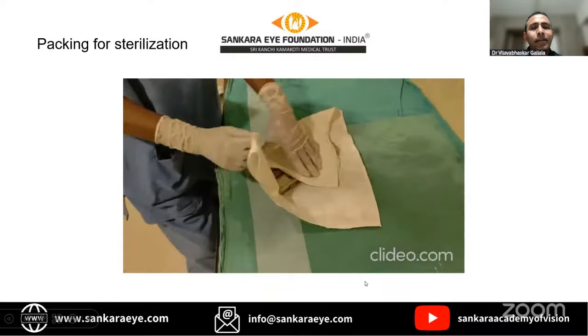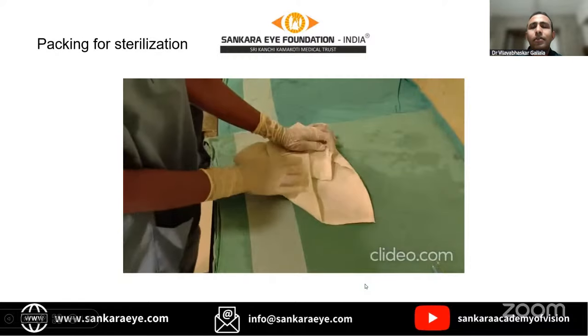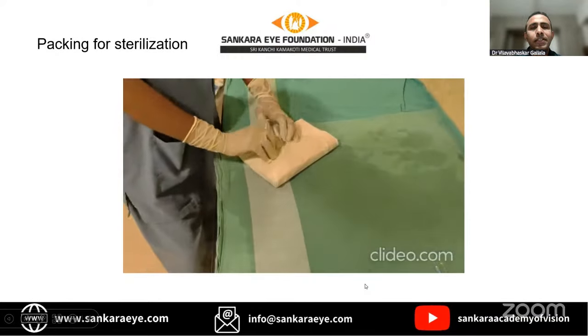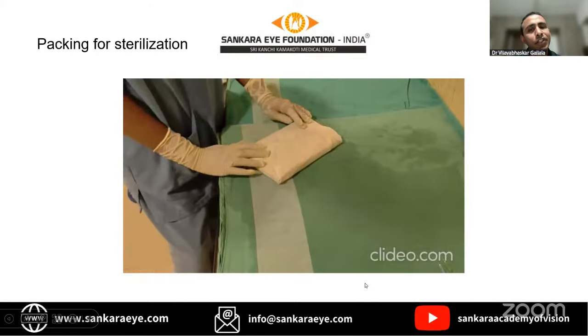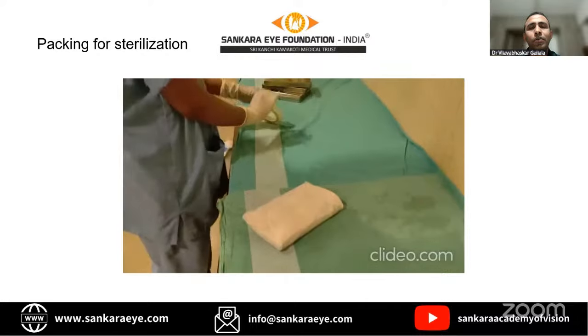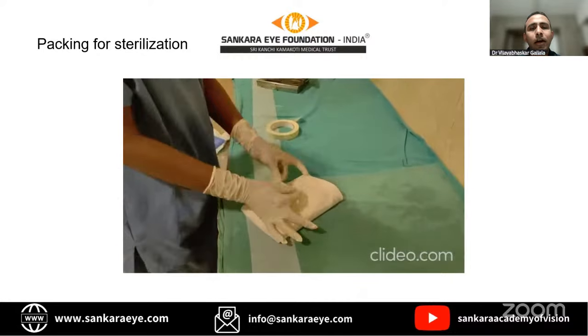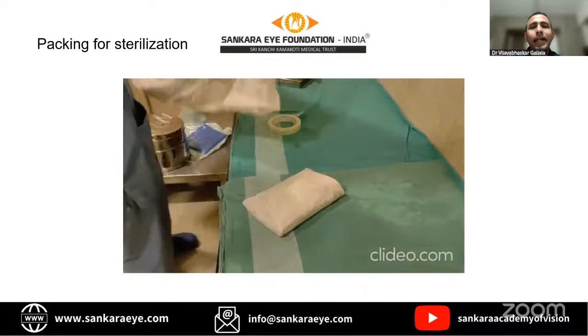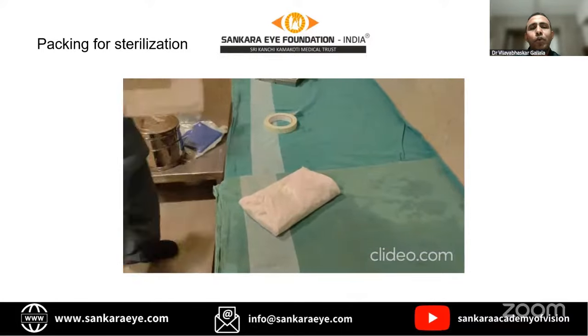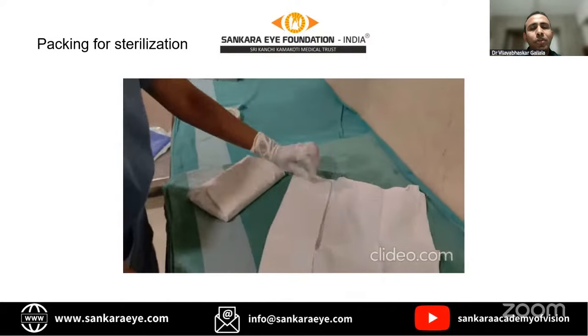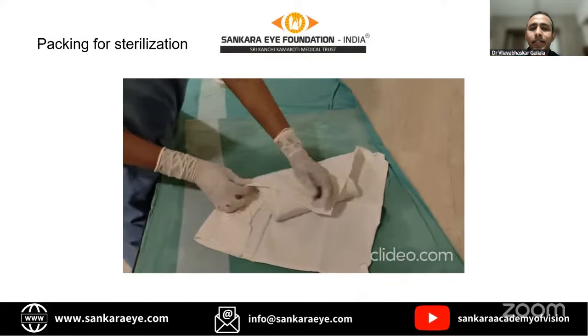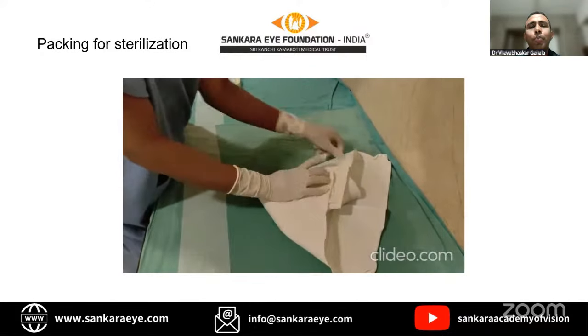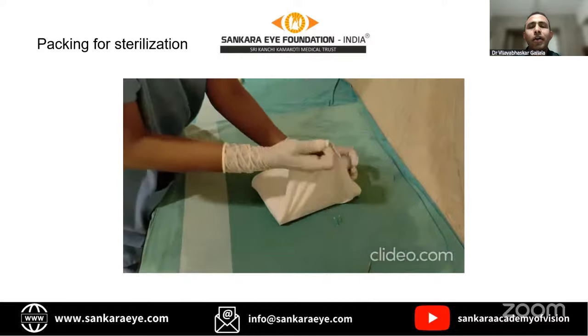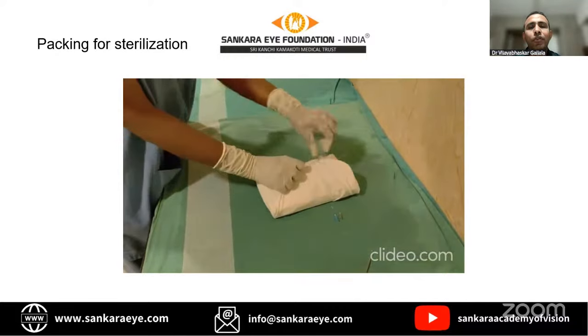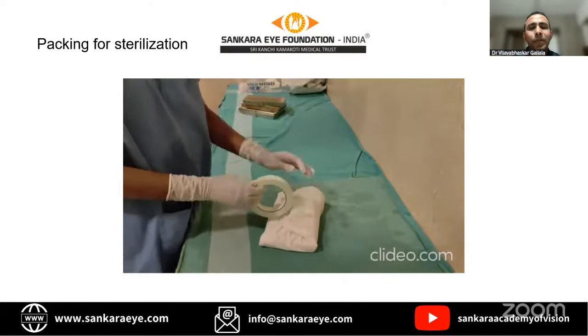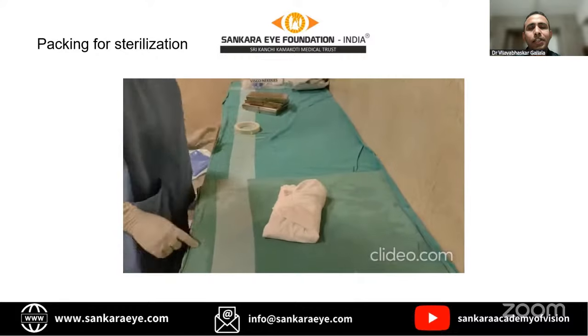So how do you prepare these instruments for autoclave sterilization? This is the packing method. The packing partially influences the sterilization also. The packing should not be too tight or too loose. Usually, the ideal is double packing. When you are packing, always make sure, as I have shown in the previous video, to keep an indicator inside the box. At the same time, you should put an autoclave signaling tape or type 1 indicator over that one. This is how you should prepare your pack before sending it for the sterilization process.